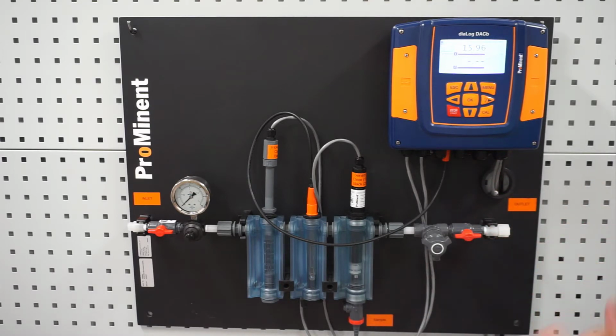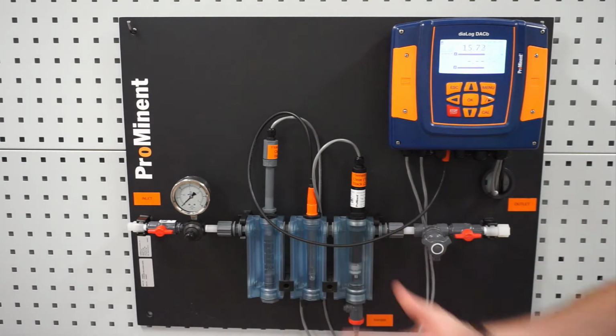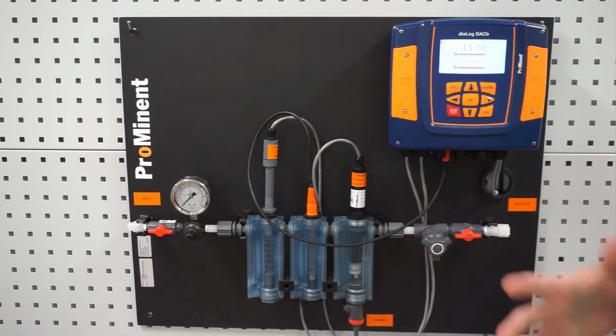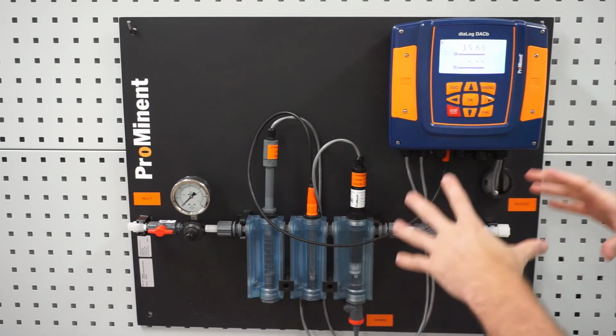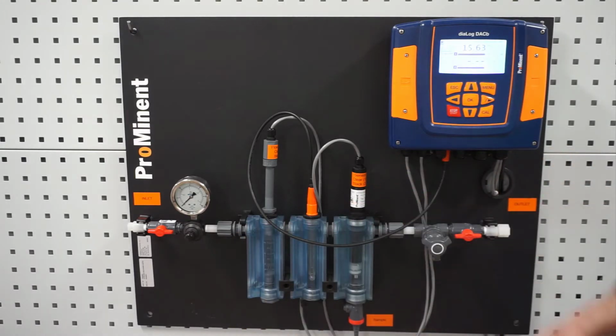Once we have water going by, the sensors need to be charged. A pH sensor typically is ready to go in maybe 30 minutes. A free chlorine sensor is going to take a little bit longer. The liquid in a free chlorine sensor is a little bit closer to water, so you may give it an hour or 2 hours to charge up. It does need to be in the presence of chlorine, so the water that is running by there does need to have some chlorine in it to create that chemical reaction with that electrolyte. So that's the first thing we want to do, is getting water by here so we can get the sensors charged and up and running.